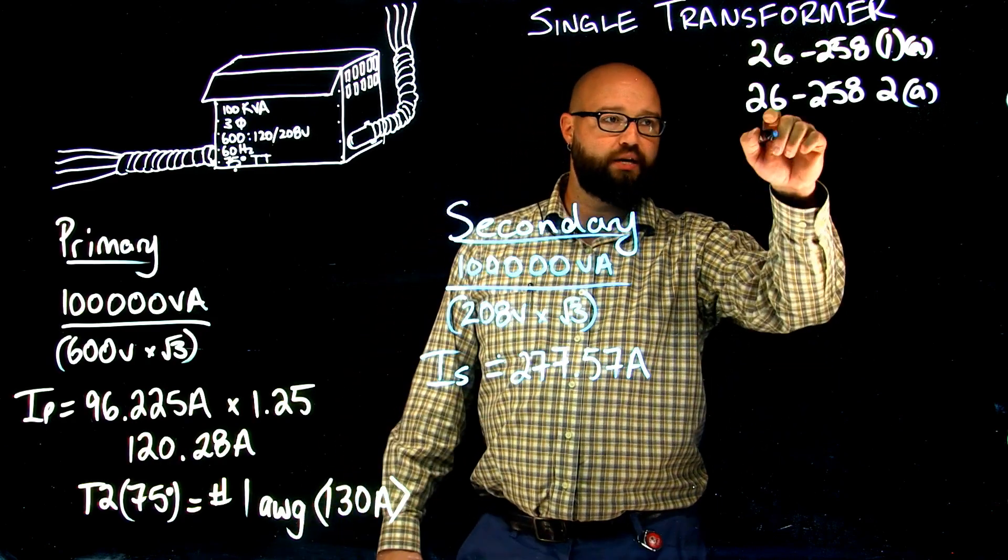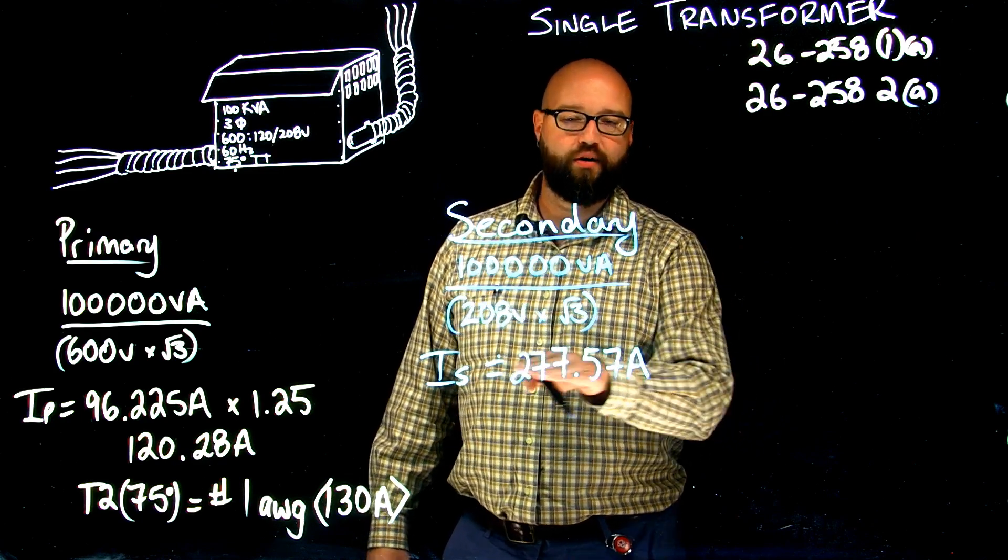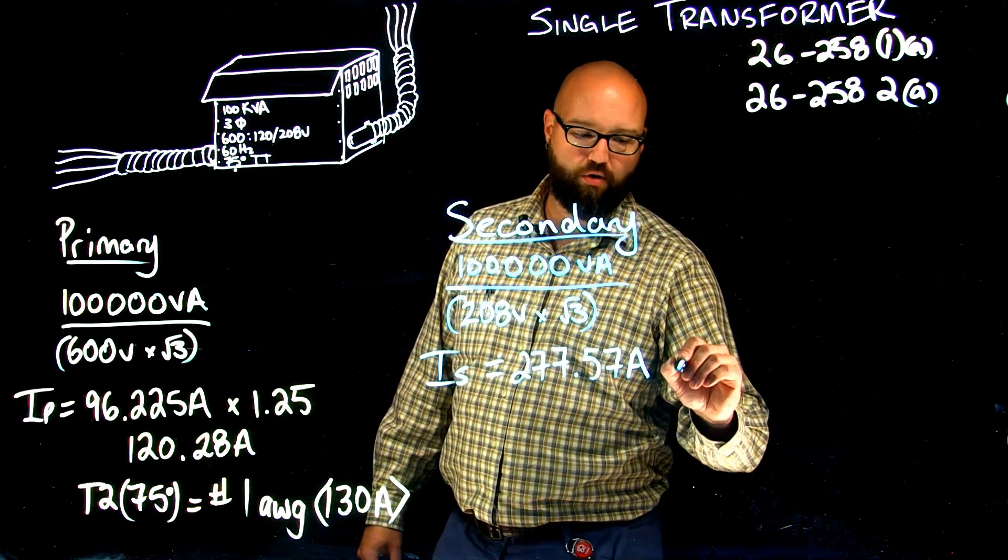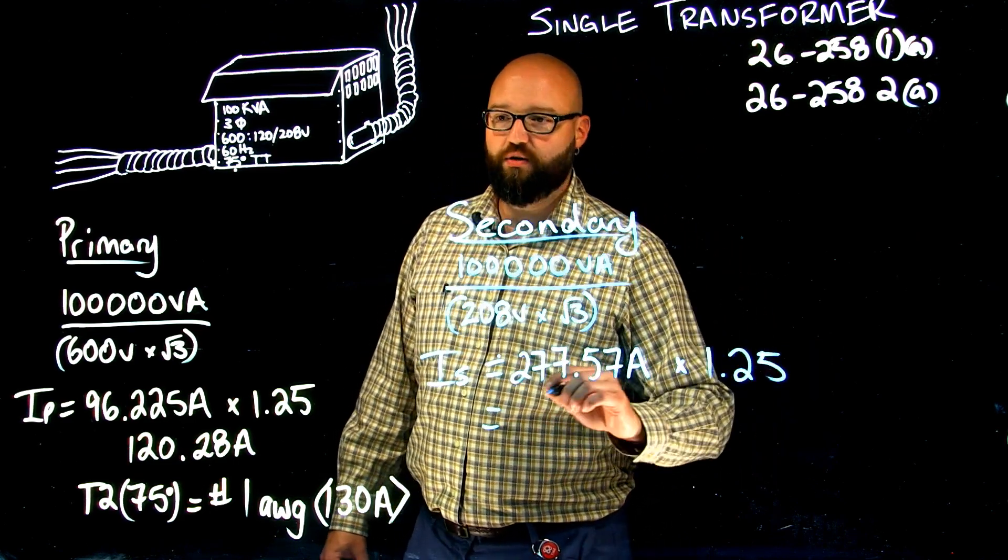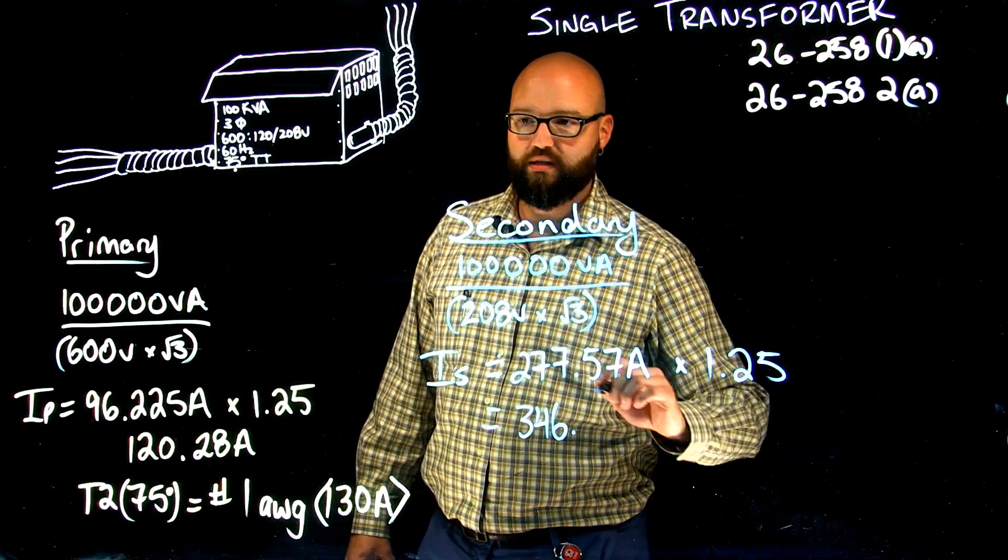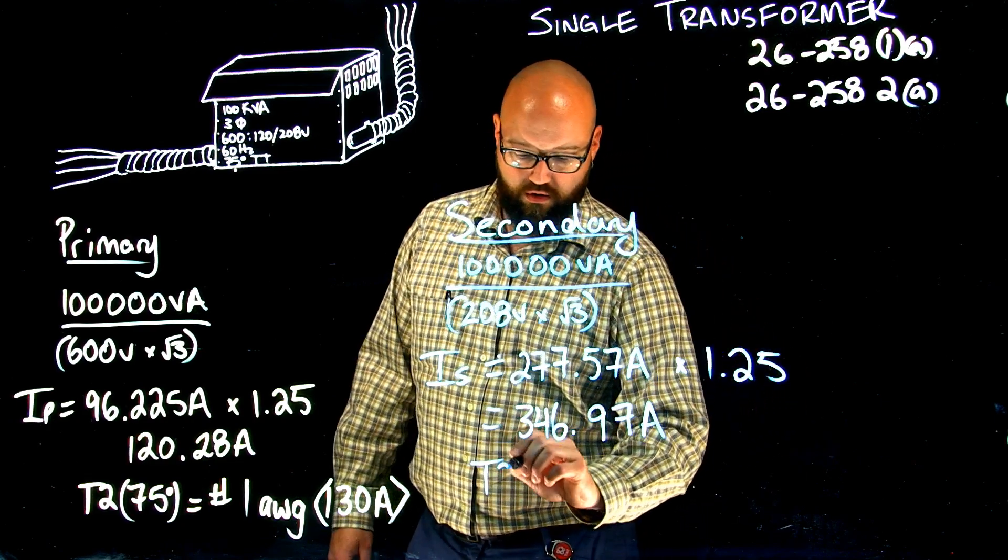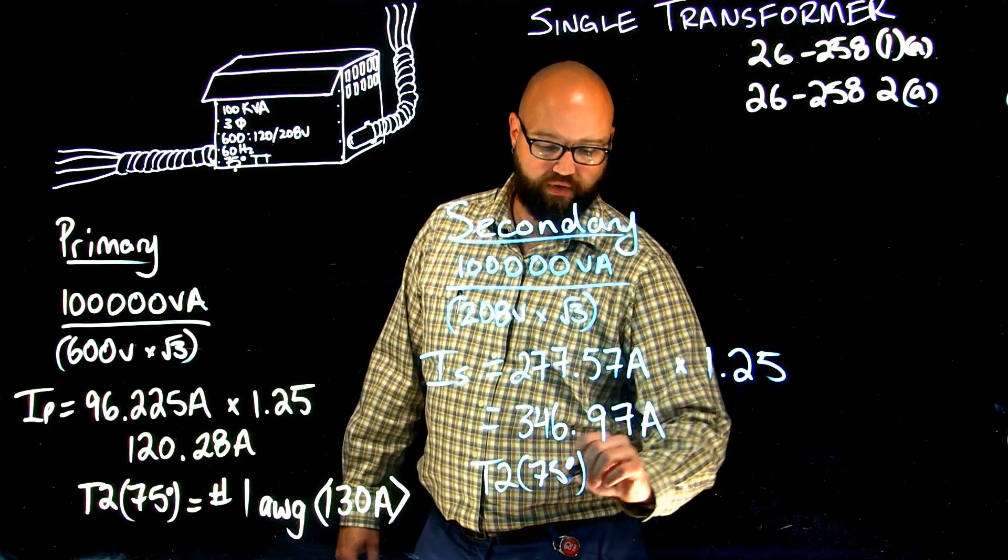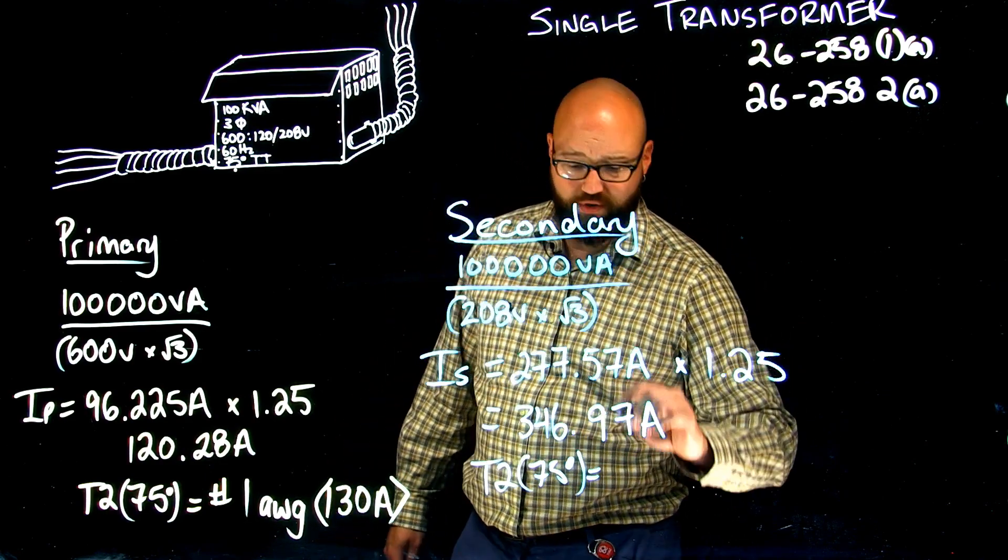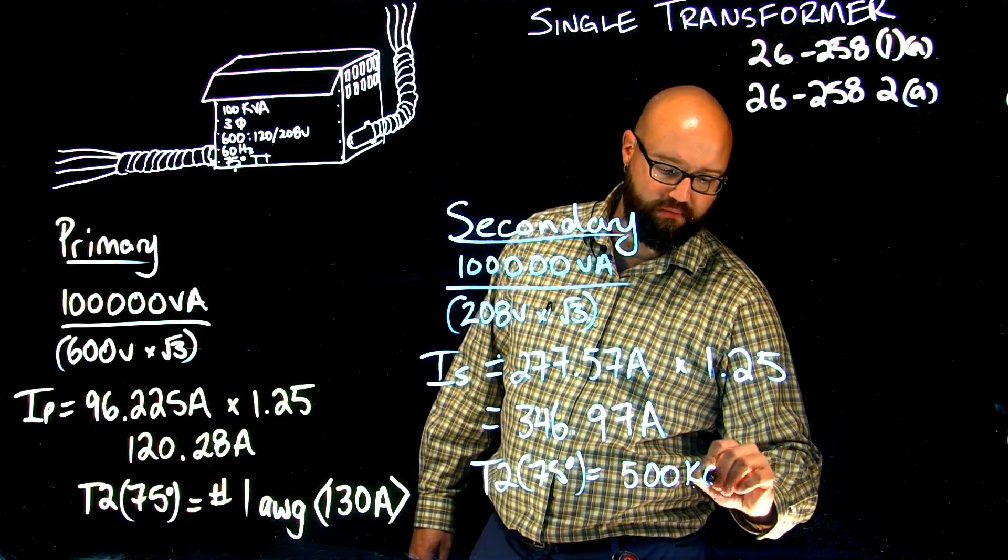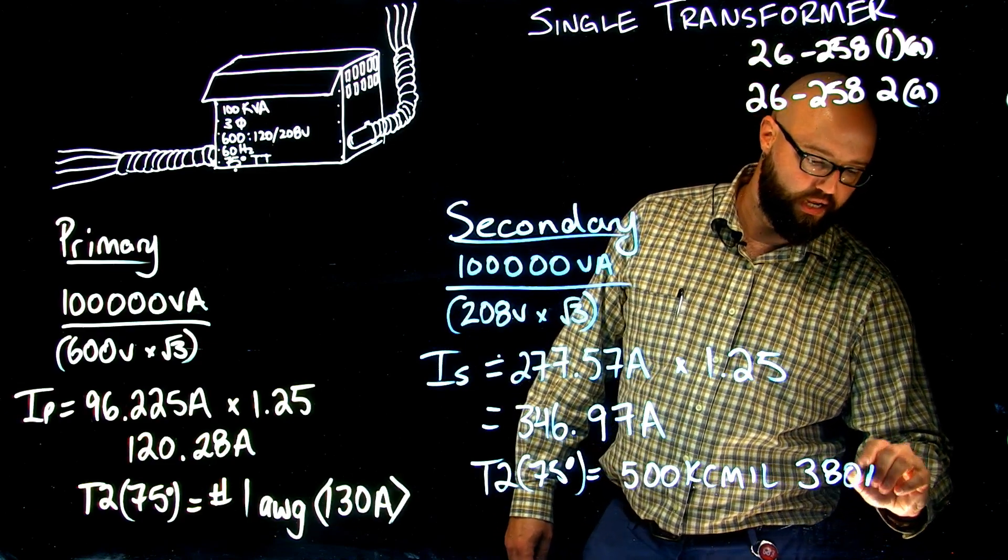And again, it tells me 26.258 subrule 2, item A, I need to have a conductor with an ampacity at least 125% of this number. So, again, times 1.25 gives me a value of 346.97 amps. I go to table 2, again, in the 75-degree column. I'm going to choose a conductor with at least that ampacity. We end up choosing a 500 KC mil with an ampacity of 380 amps.